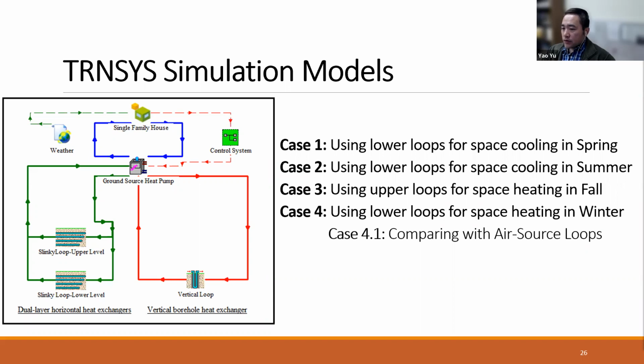Case 2 is to use the lower loop, or the lower underground region, for space cooling in summer. This is to make sure that the lower underground region is able to absorb more building heat that can be used in winter for space heating, again in case 4, where the lower loop is going to be used.